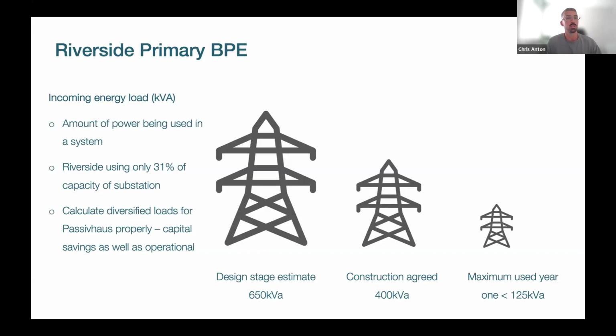But the good thing about this school is we've done our own analysis through the BPE, looking ahead to next year. Looking at peak loads, we've only gone up to about 125 maximum, so we managed to reduce it down from 400 to 199. Looking at the figures today, that's actually saved us about £700 to £800 a month just on standing charges, so we went back to SSEN, our supplier, and got them reduced.